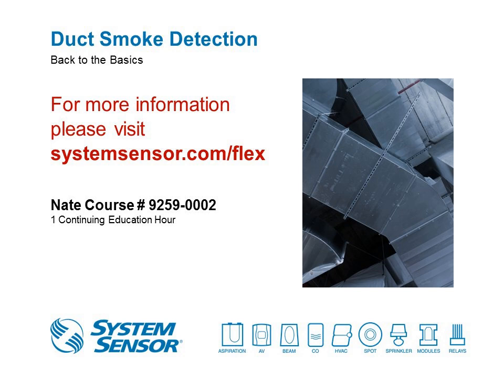That's going to depend on the AHJ. Some municipalities will allow that. Usually in an intelligent addressable panel, they'll allow that as a remote indicating device because it actually gives them a location. In most cases on the conventional side, that doesn't meet the standard. But again, that's a local municipality decision.